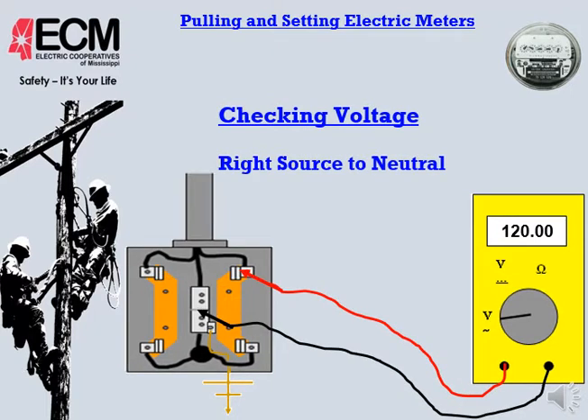It might be a little bit more than that. We're going to do the same thing on the right side. We're going to check right source to neutral, and again, that should give you around 120 volts. If you get around 116 volts on either side, phase to ground, that's going to be on the low side. So that's going to give us another problem that we're going to have to deal with.